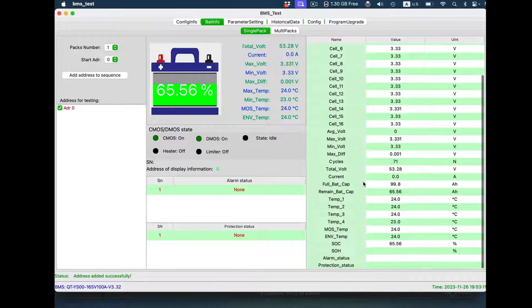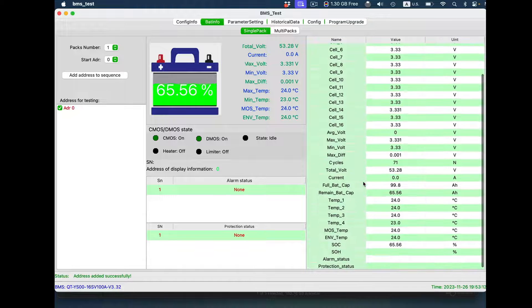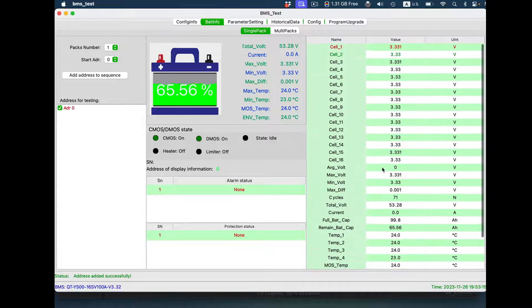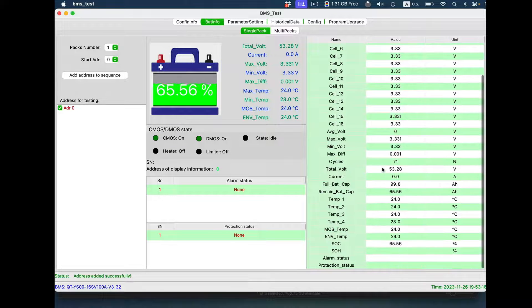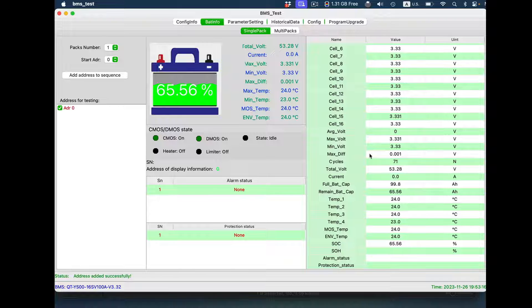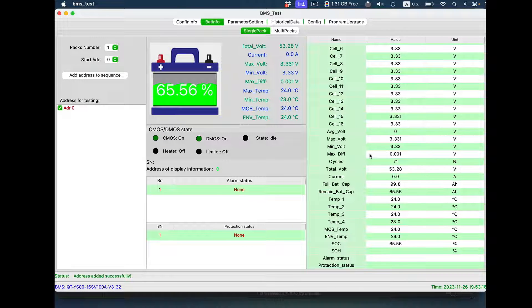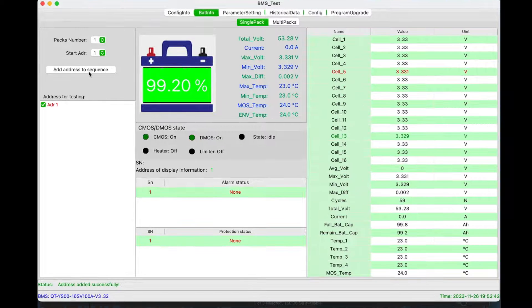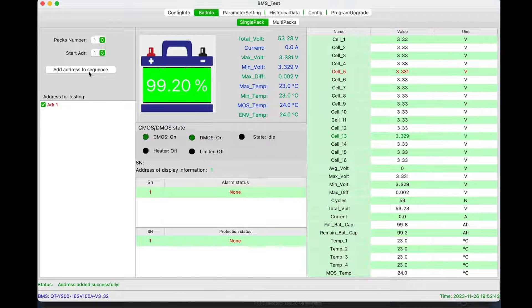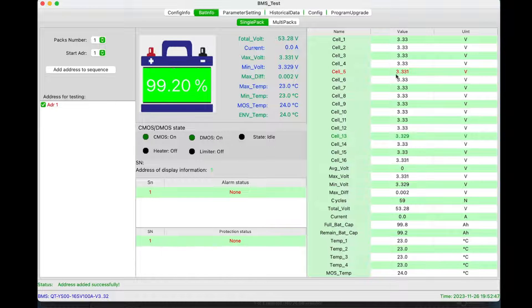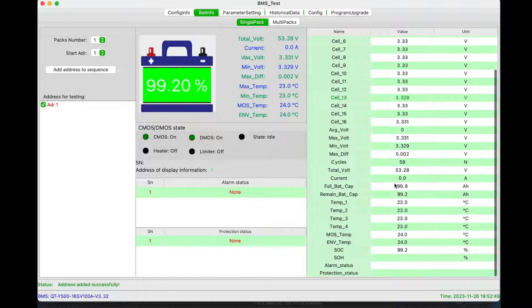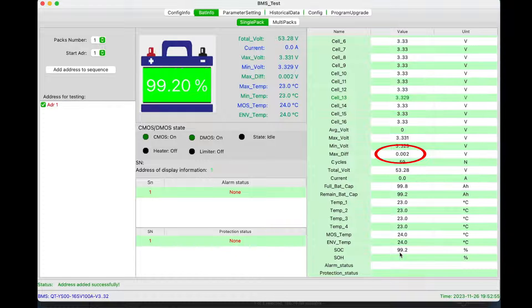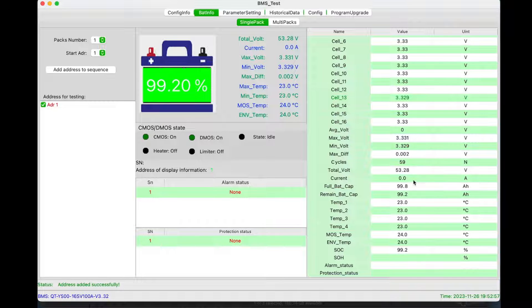This is BMS Tools from EG4, actually available on Mac now. The cells are all running about 3.33, and the difference between the highest and the lowest is one one-thousandth of a volt. And this is the second battery, and the cells are almost identical, 3.33. The difference between the high and the low cell is two one-thousandths of a volt. So the cells are almost identical in the two batteries.